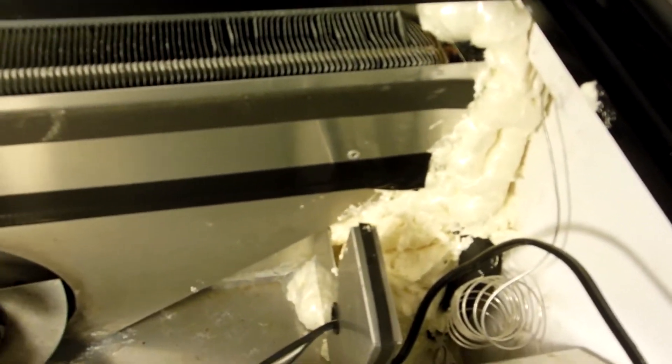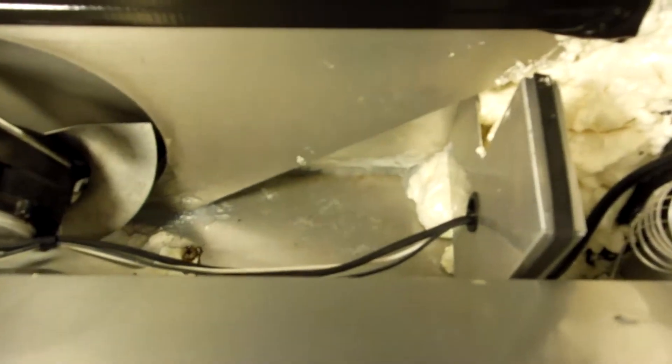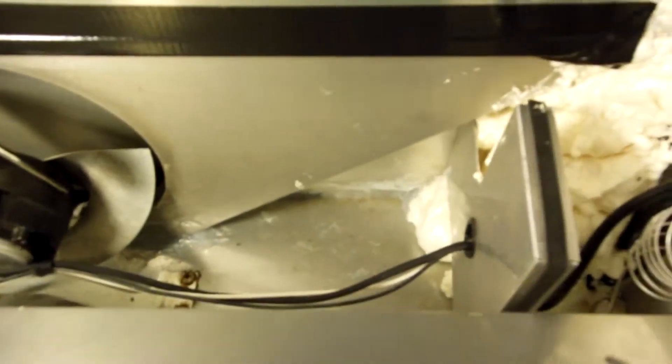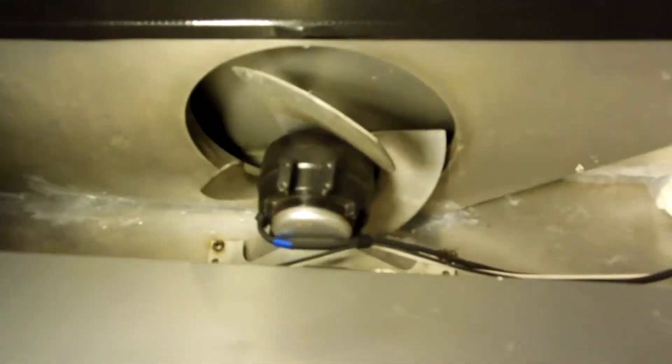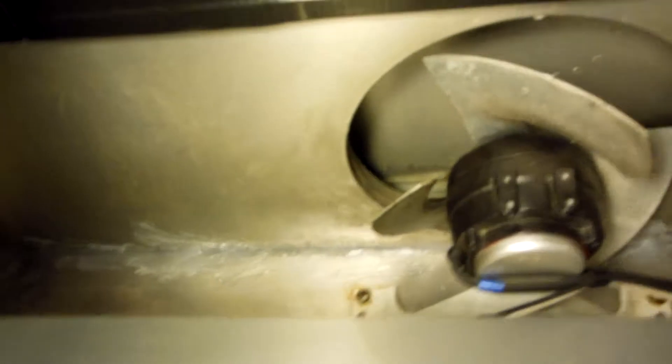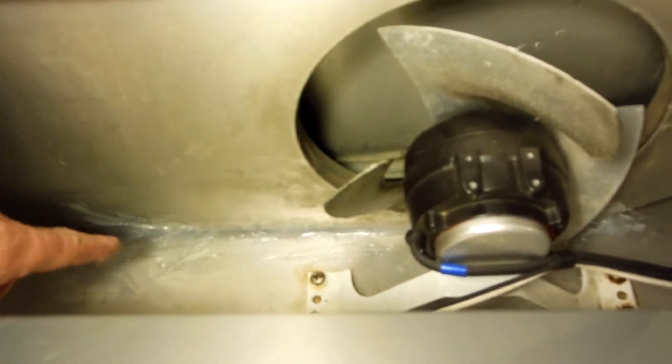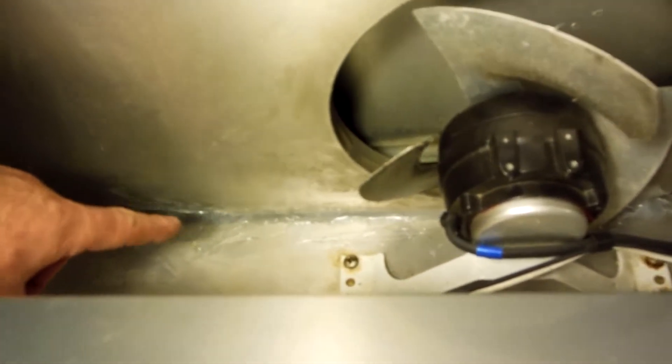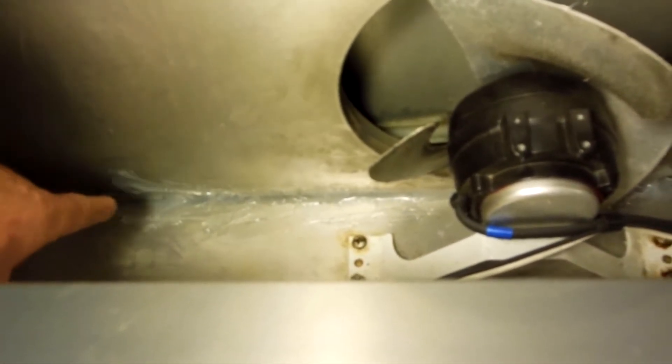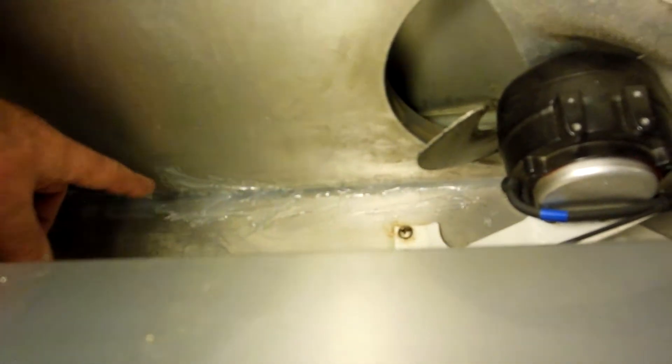And also I just siliconed. Actually I found out what the major problem is, what I believe it is. I saw a hint of corrosion starting - aluminum, where the aluminum gets pitted along the bottom corner of the evaporator.